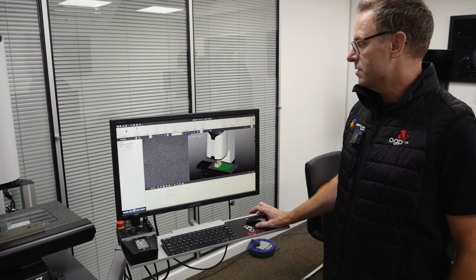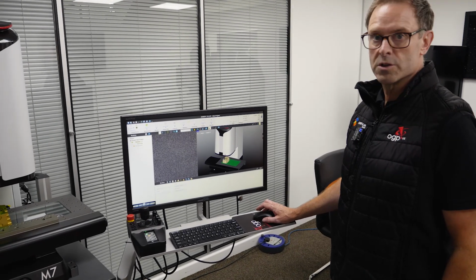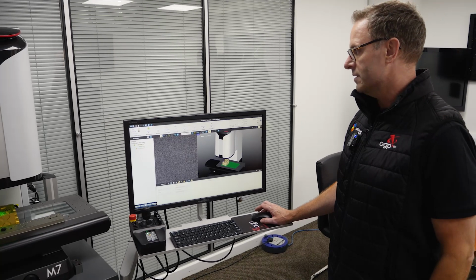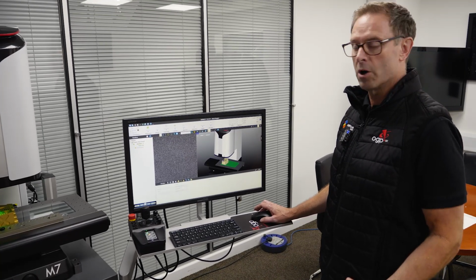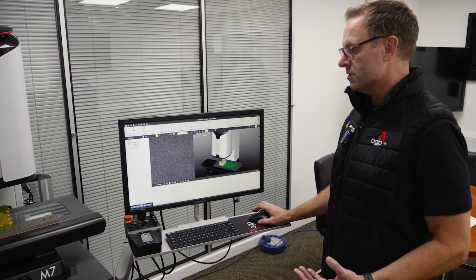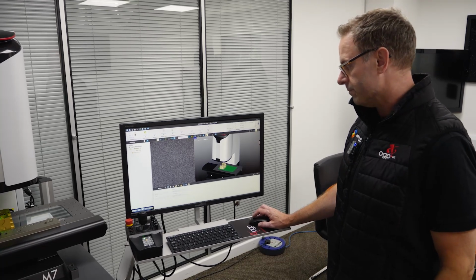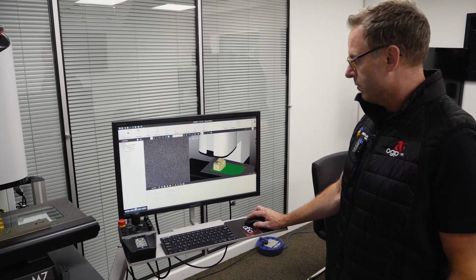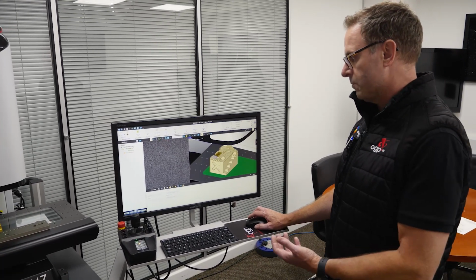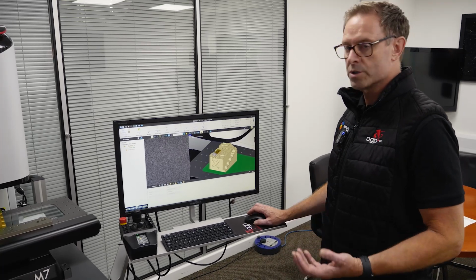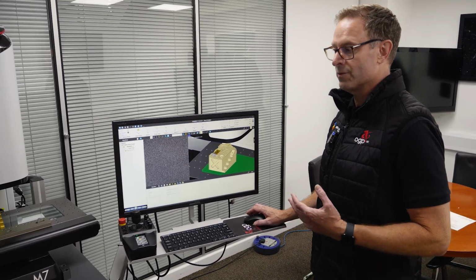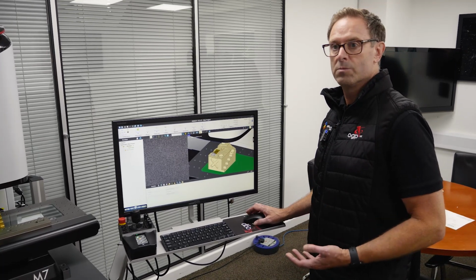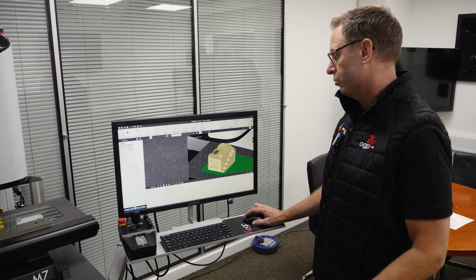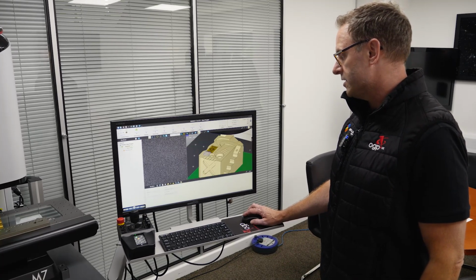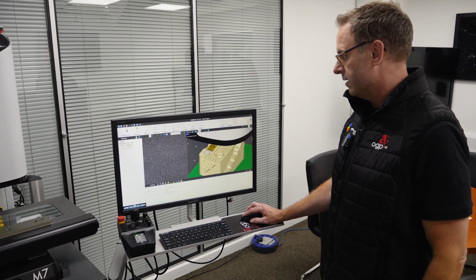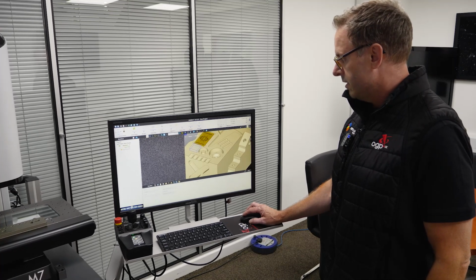The M-Series uses the Zone 3 software platform, so it is a CAD model-based programming platform, one of the most powerful on the market. You can see I've brought the machine model in, I've got the CAD model in there. We can also offer offline programming, and that is for every sensor, whether it's optics, laser, touch probe or rotary. It's very easy to program. Once you've brought your CAD model in, let me just turn the machine off.